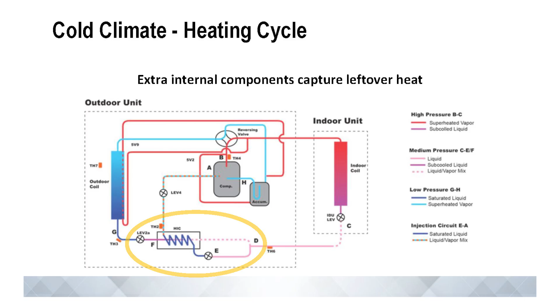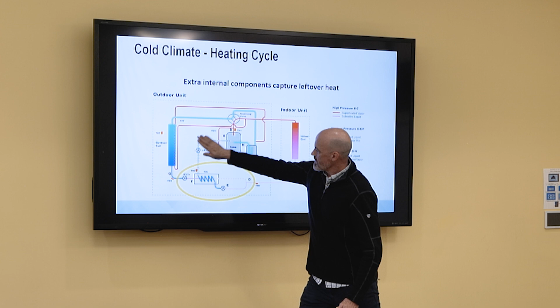It's saying, well, this is the indoor coil. I know I have a little extra heat that's leaving that didn't get used, because it might come in at 140 degrees. We might get 30, 40 degrees off that coil, and now it's about 90 degrees or something like that here. Well, it's going to take that, move it through this expansion valve and separator, and separate the remaining liquid and vapor. And it's going to say, I'm going to use this liquid here that's colder than the vapor, and I'm going to extract even more heat from this. But I'm not delivering it into the house. I'm delivering it back into the system out here. So it's just capturing waste heat. That's all it's really doing.